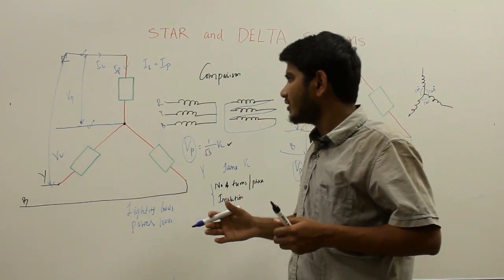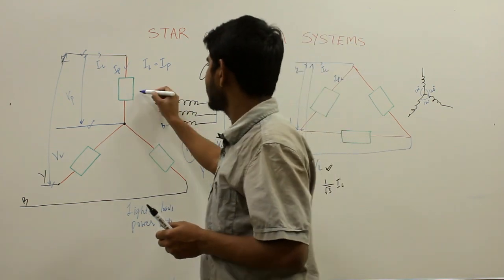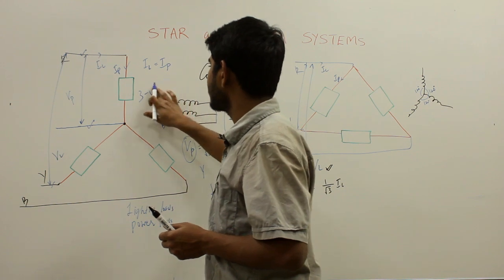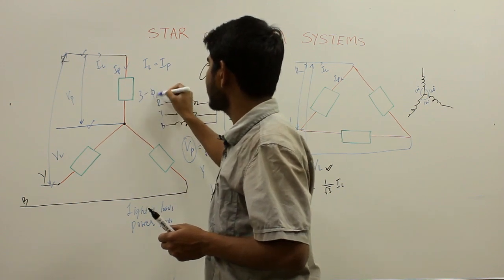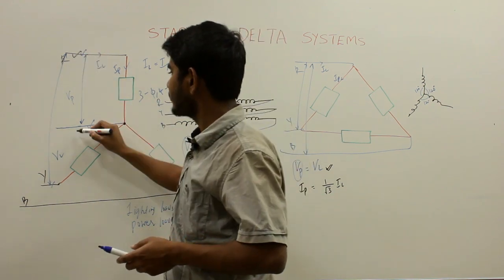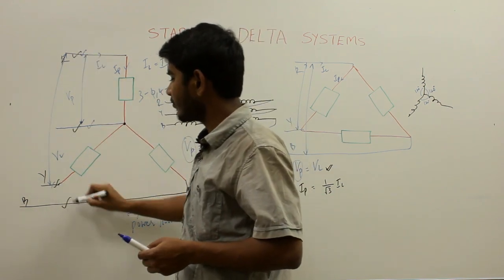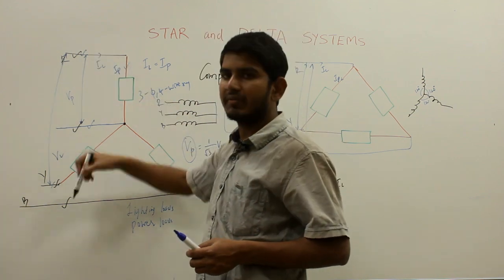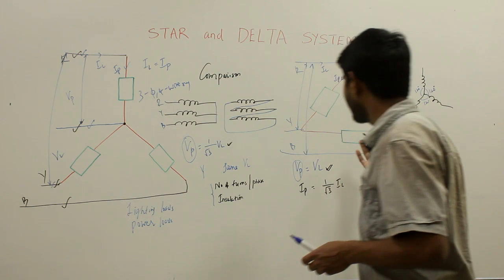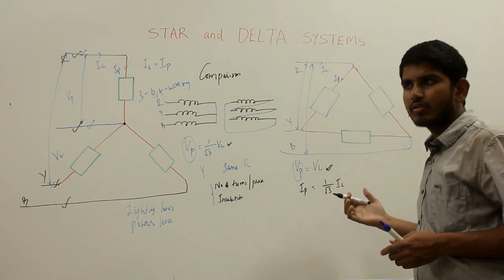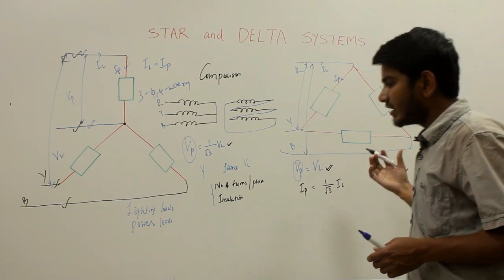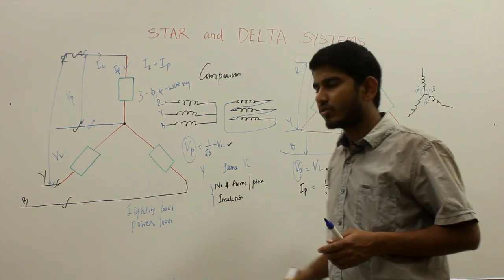Power circuits are connected between the lines. This arrangement is called a three-phase four-wire system — three phases plus the neutral wire going to the load end makes four wires. In the delta connected system there is no concept of neutral, so delta is not used to supply household loads.